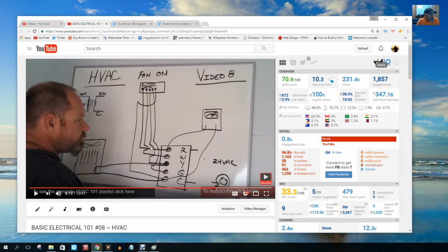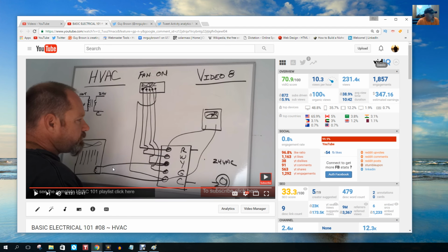It's just nothing. So when you get a call for cooling and that power is coming down on the Y wire, what they did on Chris's furnace is they just wire nutted it right here and sent it on out to the condenser. So the power is going down G to the furnace to turn the fan on, and the power is coming down Y and connecting right here and going over to the condenser, and the other side of the condenser is common, so that completes your circuit. That's it. Basically, Y is a dead terminal, there's nothing there, and it can just easily be wire nutted right there.